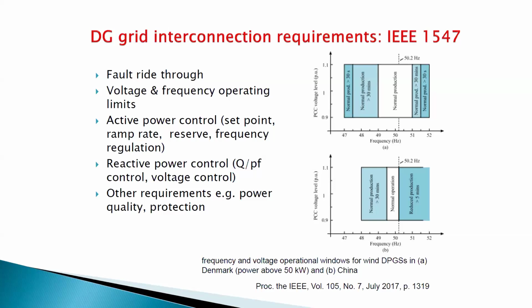We talk about the reactive power control. Reactive power is very much associated with voltage balance and voltage control in the power system. As we talked about, you have to maintain voltage within plus minus 10% of the nominal voltage. This voltage will basically depend upon how proper a balance we have between the reactive power generation and reactive power utilization. If there is a significant mismatch, it will be reflected in terms of voltage variation.